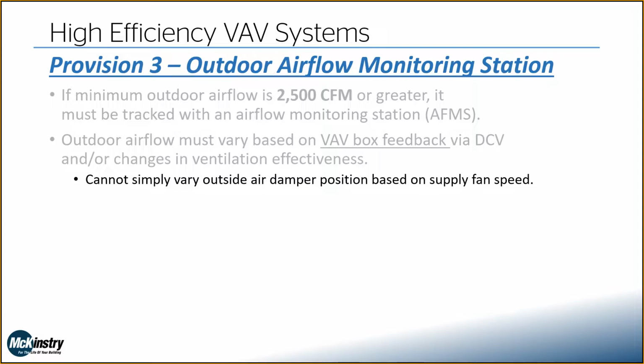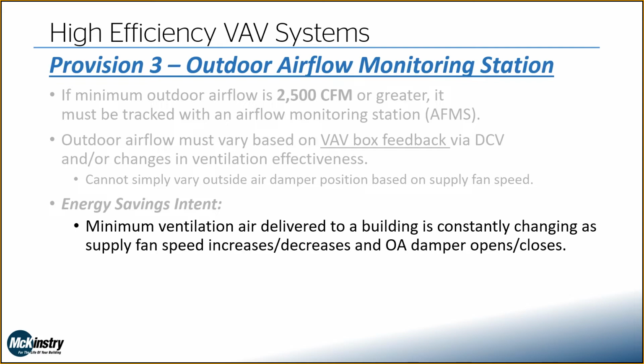A big point here is we can't simply vary that outside air damper position based on supply fan speed, which I've seen many sequences do exactly. You balance it at the low speed, you balance it at the high speed, and then you just interpolate between the two. But in this case, we need to actually vary that based on some feedback from the VAV boxes. The intent here: our minimum ventilation air that we're actually sending out into the building is constantly changing as the supply fan ramps up and ramps down, and the outdoor air damper opens and closes. You have an infinite amount of permutations where you don't really know how much ventilation air you're bringing in.